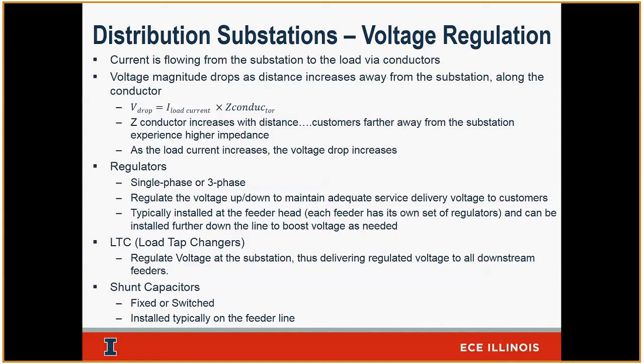Another tool that we have is a capacitor. The capacitor typically controls VARs, and VARs help boost the voltage up and down depending on how you use them. If you close a capacitor bank, meaning you dump more capacitance on the line, you're most likely bringing the voltage back up. If you open that, if you take that capacitance out of the line, you're typically bringing the voltage down. We'll talk about how these are used as technologies to optimize voltage on a circuit maybe one of these days.